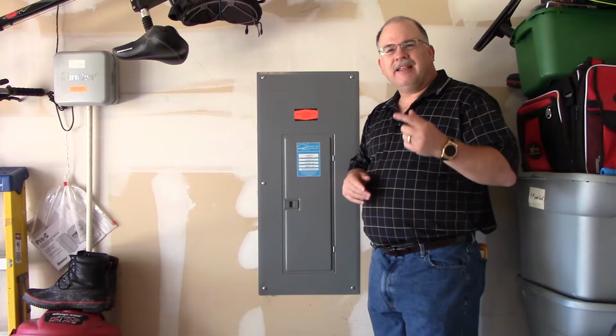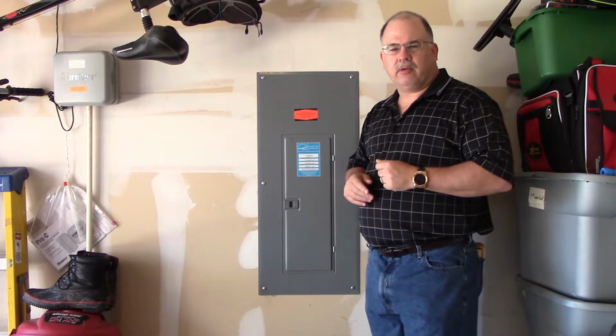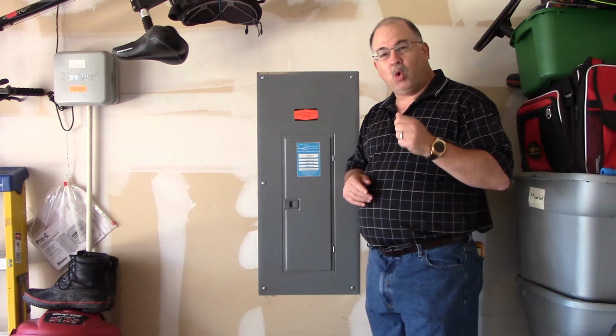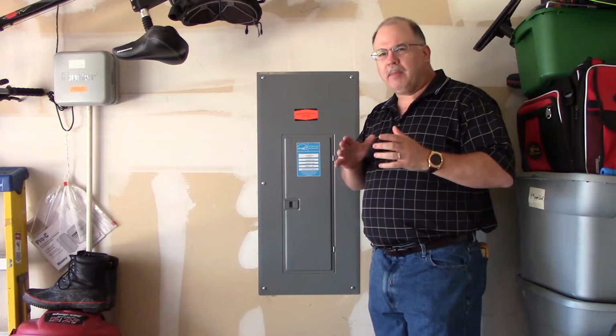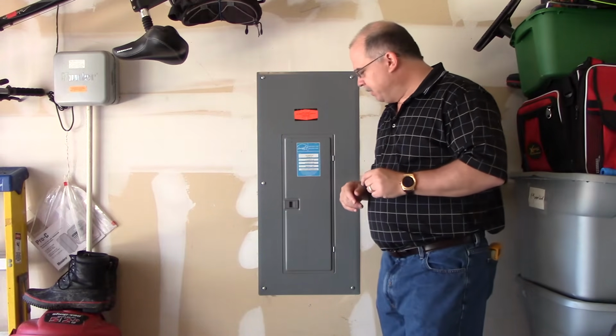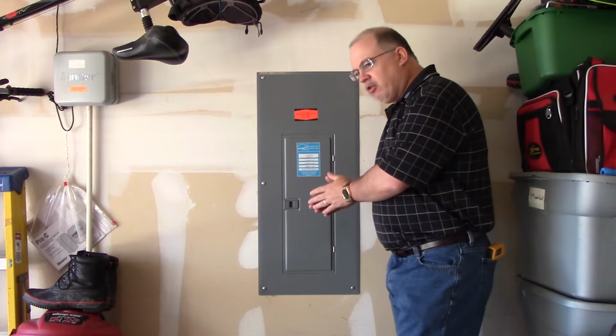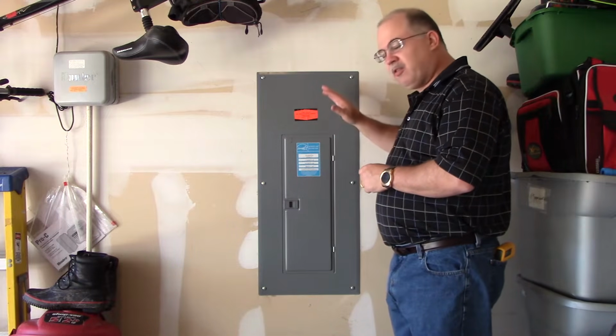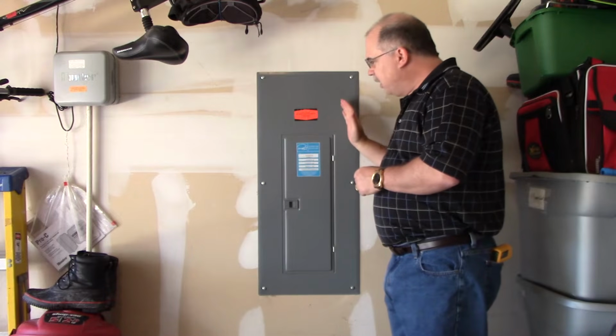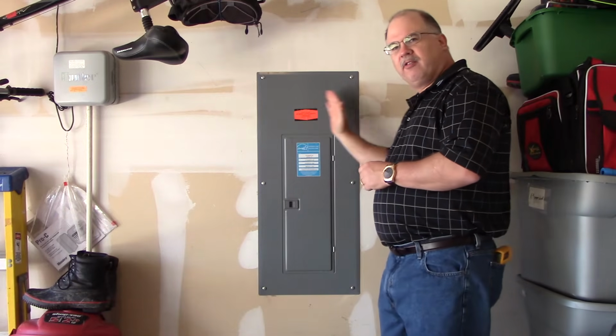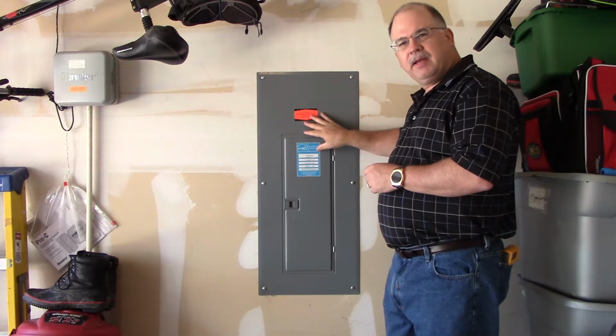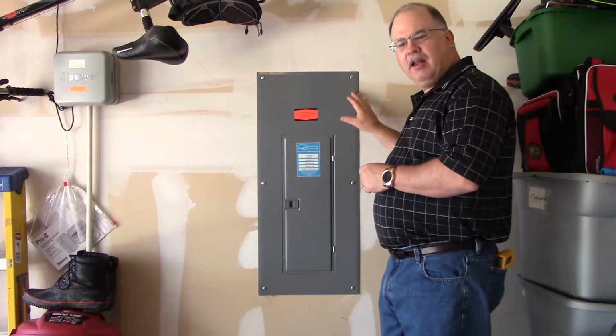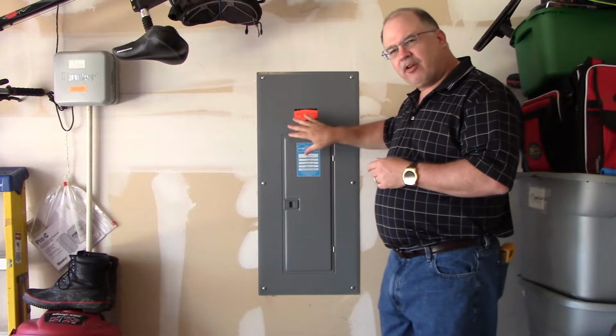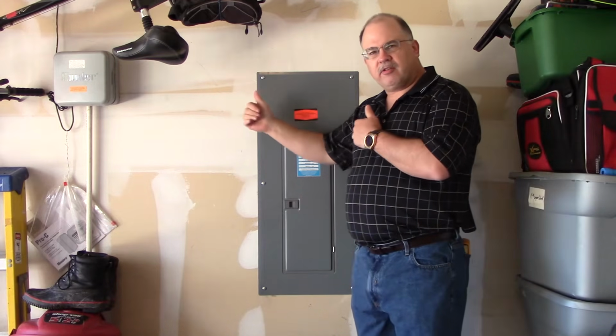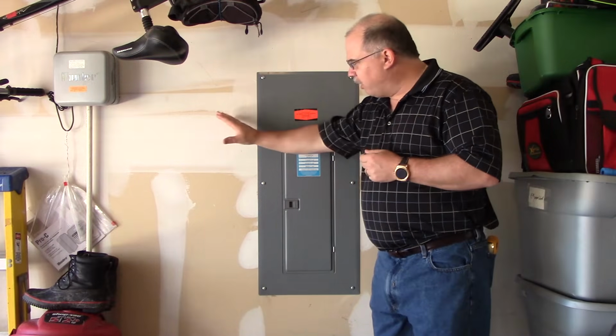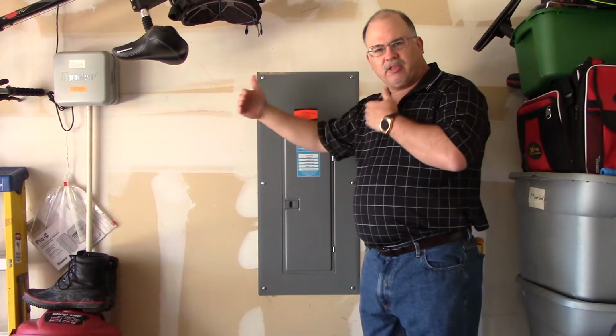have good space here. Now, the National Electrical Code does give us some guidance on that. If you look at section 110.26(A)(1), (2), and (3), you're going to find the requirements to maintain this safe working space. Now, the clearances that are involved in the National Electrical Code is generally the width. Now, the width is going to be, this panel, for example, is designed to fit between the stud framing members. So, you want to make sure that it's 30 inches of clearance, left or right, for this panel to be in. Now, it doesn't matter whether it's to the left or to the right or in the center of those 30 inches. We want to have at least 30 inches or the width of the panel. In this case, the 30 inches is going to be the minimum for this size panel. So anywhere in here is what you're going to have allowance for that 30 inches.